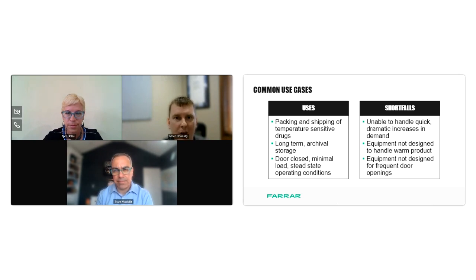So your compressors end up running extended runtime at high speeds, which then reduces the reliability of them long term, which then ends up meaning that the equipment could fail sooner than expected. So typically the equipment's not designed to handle either warm product, excessive door openings, because that also translates to a bunch of heat transfer from the exterior of the cabinet into the interior of the cabinet. And then just the dramatic change of load if you put warm product in when you've already frozen down the freezer, that has a big impact to its operating efficiency.